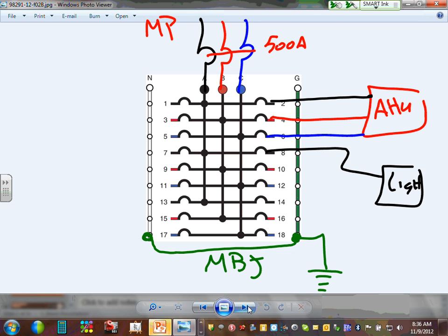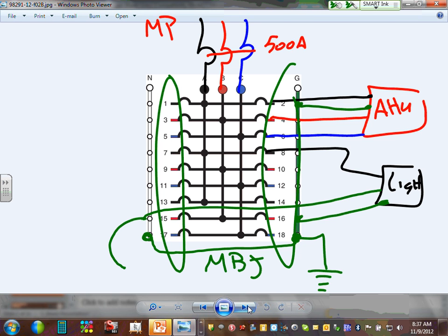A neutral. Where's my neutral? Let's use a neutral, this one. And I need a neutral. How am I going to get the neutral there? Neutral. Can I have thumbs up, Chad? We fully understand this. That's what I want you guys to understand. Please. So phase A, B, C, ground, neutral. I need also to take a ground. Here's my ground here. And also you always take a ground to the equipment. That's how you circuit in the panel. That's what you guys did with me in Revit. You did with me in CAD. From left to right, ABC, neutral, ground. Thumbs up, Chad. Top to bottom. The odds are on the left, evens on the right. Any adjacent two circuit breakers are coming from two different phases.